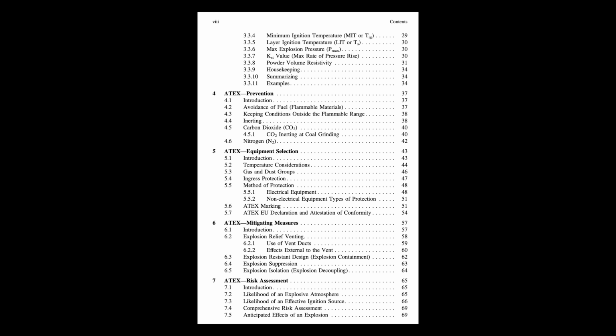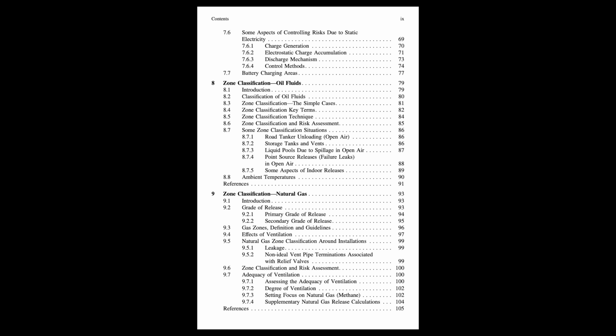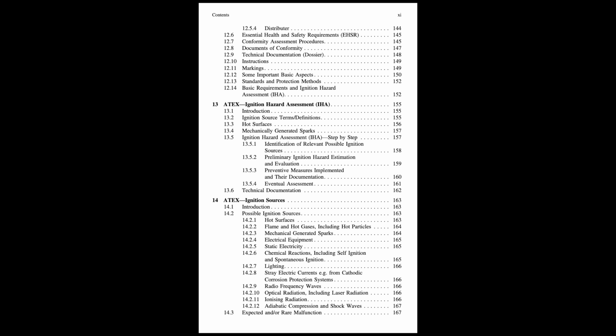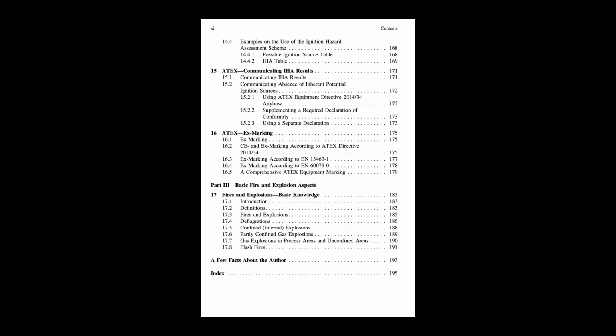Okay, and our guide looks at both CO2 and nitrogen for this. Let's start with carbon dioxide. What are the key things to know about using CO2 for inerting? Well, the guide points out CO2 is relatively inert, meaning it doesn't react much with most common stuff. It's already in the air, just in tiny amounts. Right. One thing to watch out for, though, is if moisture is present. CO2 and water can form carbonic acid, which can be corrosive over time. Okay, good point. And how is it usually stored? Typically as a liquid under pressure. You might have big refrigerated low-pressure storage tanks or sometimes smaller high-pressure cryogenic cylinders.